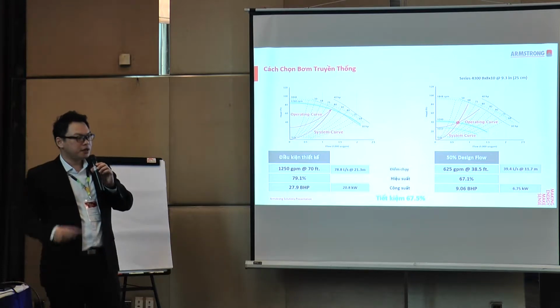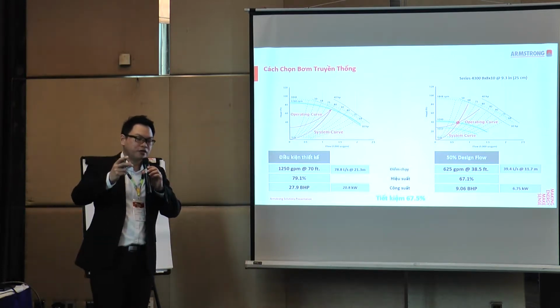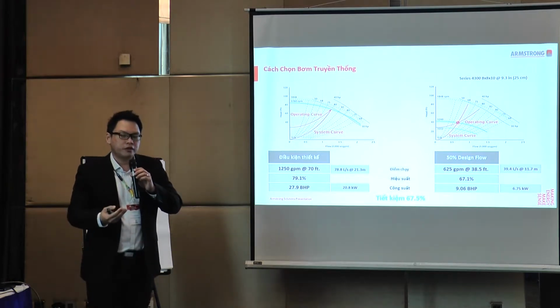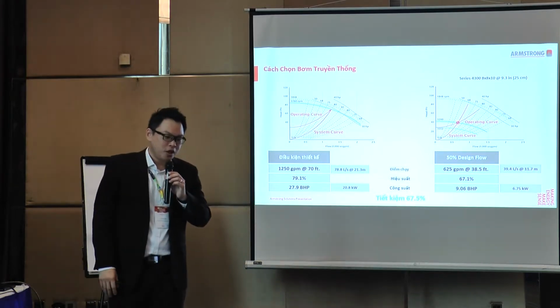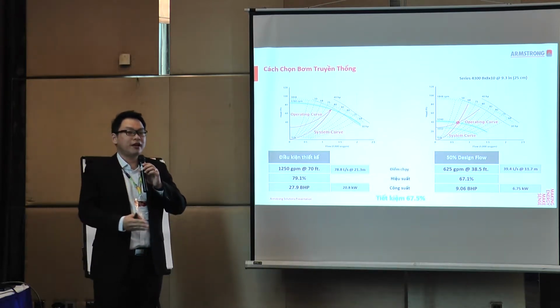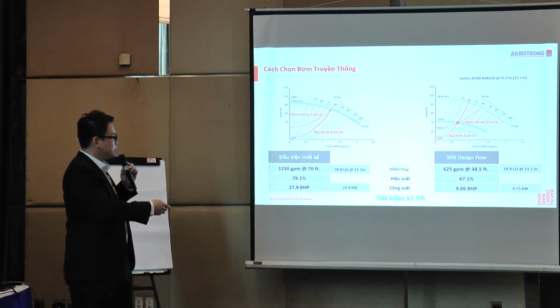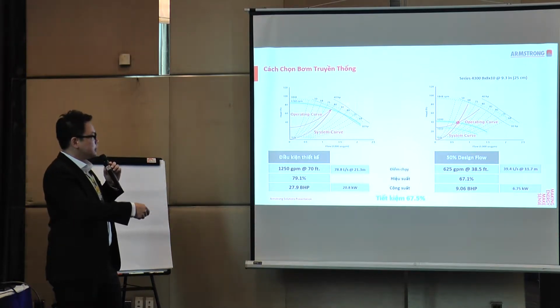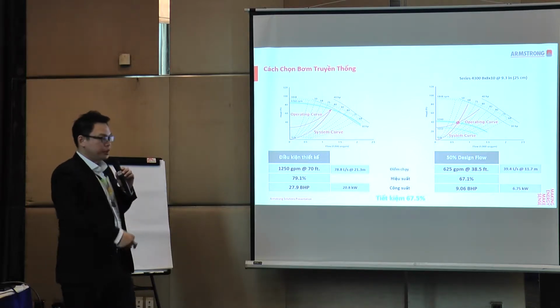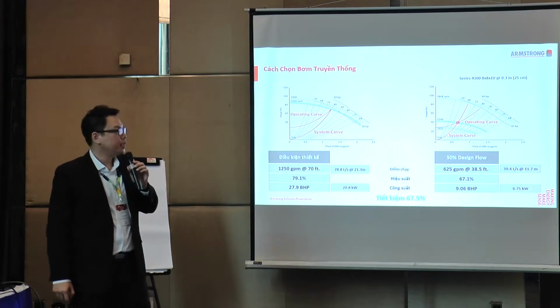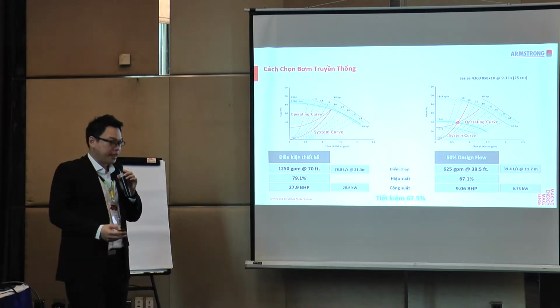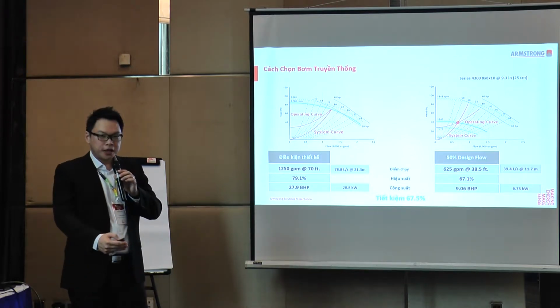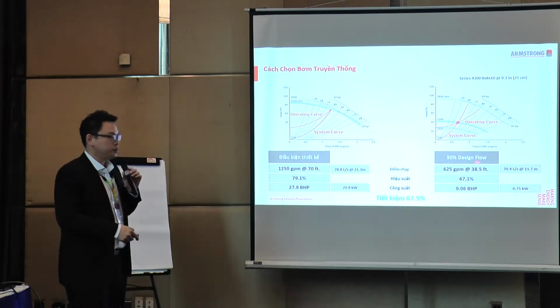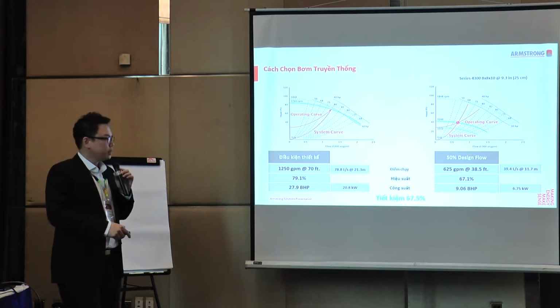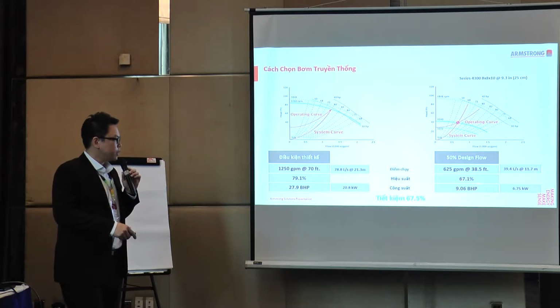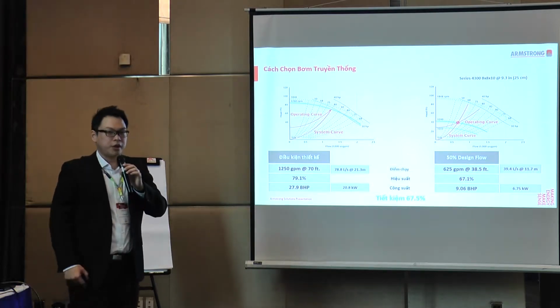Next, another mindset shift for you. Traditionally, if you approach a lot of other pump manufacturers, they select a pump that is to the left of the best efficiency point. If you follow this graph on the left-hand side, the best efficiency is around 82, but the operating point is to the left of the BEP. This is at full load, 100%. Since HVAC is a part load industry, we drive it down to 50% of the design flow. These are the readings: the efficiency is 67.1% with a 9.06 brake horsepower.